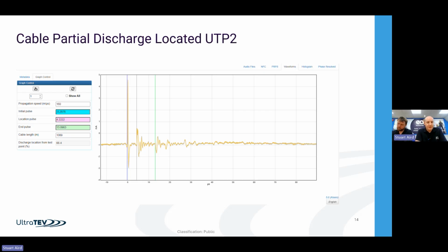We can then speak to the customer. This particular cable is XLPE, so we expected a joint to probably be in the location that we're picking up the partial discharge from, because partial discharge is quite rare in just an XLPE cable along the cable route. So then we can compare against the customer's records of the circuit, and we identify that this is in fact a joint location. The maximum recording was around 2,000 picocoulombs, so that is just getting into amber for XLPE joints. We say anything over 2,500 is actionable.